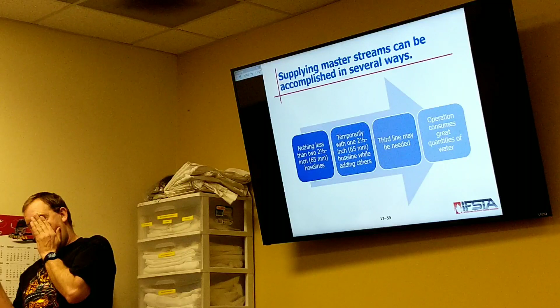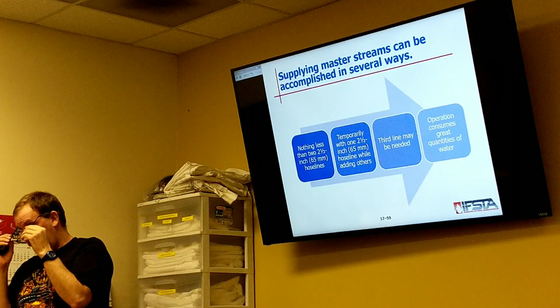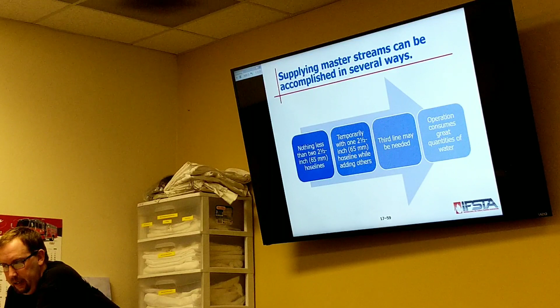Master streams are effective on water, putting an effective stream on the fire just because of the amount of water they run at a time. You're talking two 2.5s running through a master stream on a deck gun when it's deployed, nothing less than two. You can use one to begin with just to get it set up until you get the other line done. If you've got one of the big fancy ones that can put a third line to it, put a third line to it.